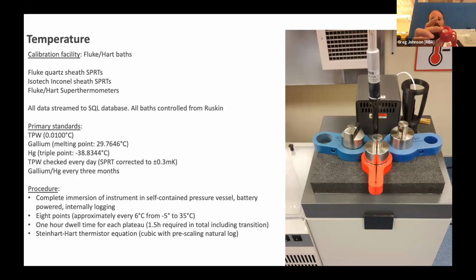However, the conductivity cell also has a thermistor inside it, because we're providing, and you'll see a little bit later, a temperature dependence of the ferrite that is inside an inductive cell. So we calibrate the marine thermistor and the conductivity thermistor that's buried inside. And then, as I was saying, pressure sensors also are very good thermometers. And so we calibrate the pressure sensor with another effectively thermistor. So there are 3 temperature calibrations occurring every time an instrument goes in the bath. Only one of them will ever be stored and read out, but the other 2 are used internally to correct the behavior of the conductivity cell and the pressure cell.